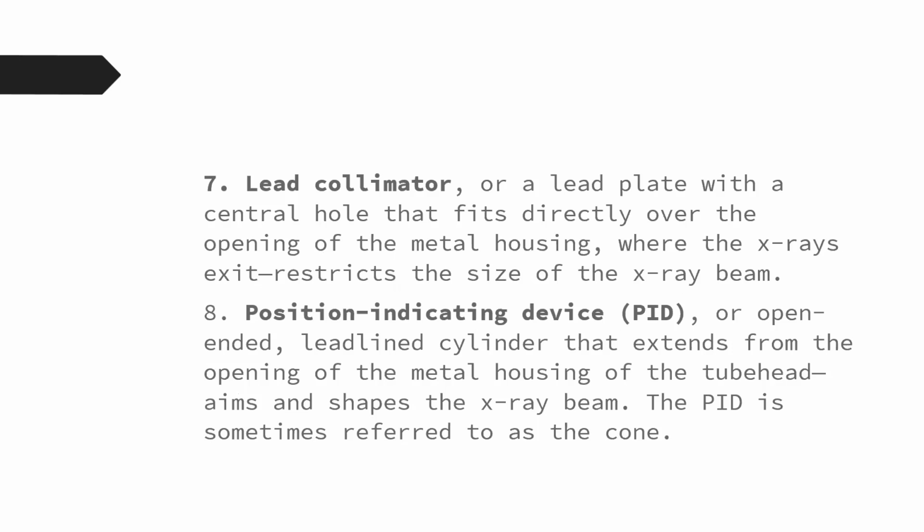So we have the lead collimator, and this is a hole that fits directly over the opening of the metal housing where the X-rays exit. So it restricts the size of the X-ray beam, right?